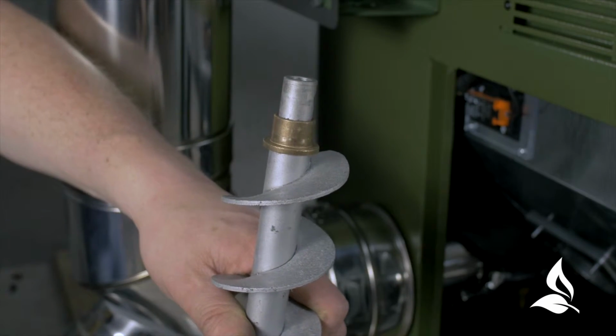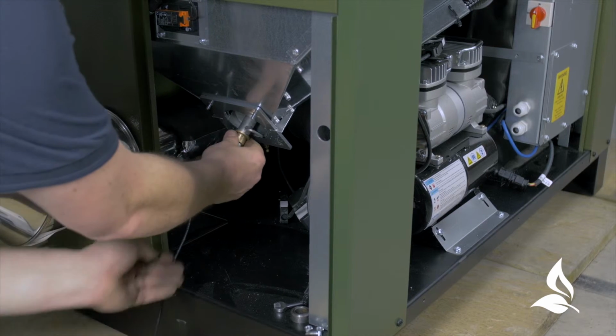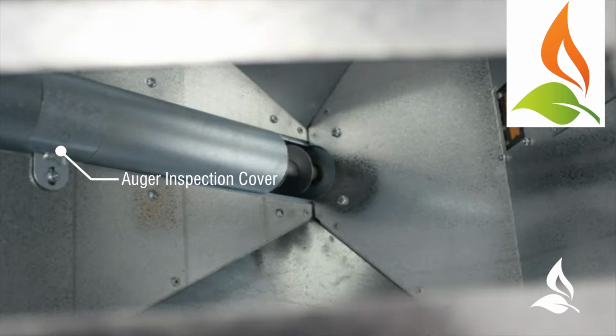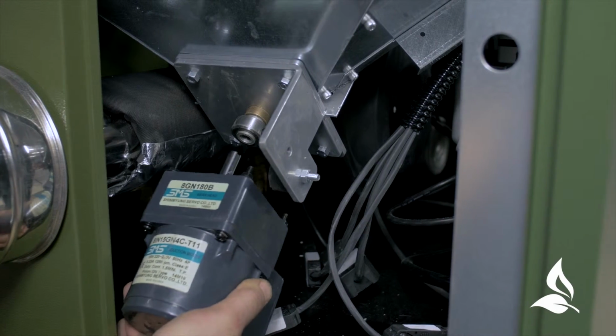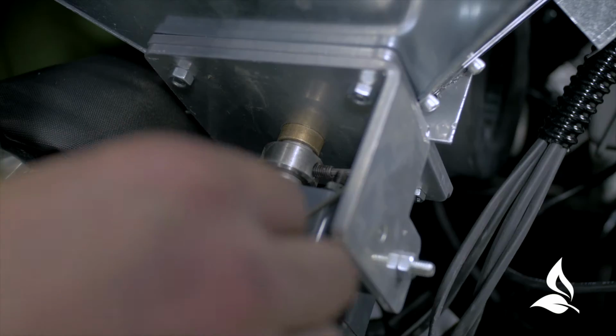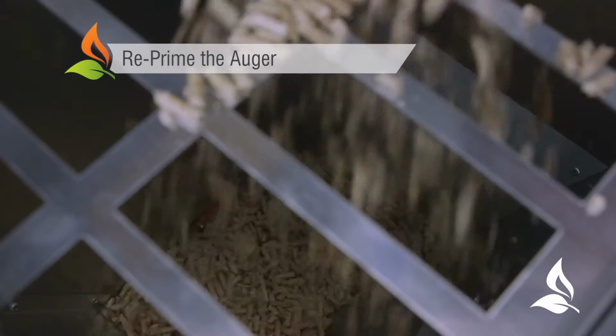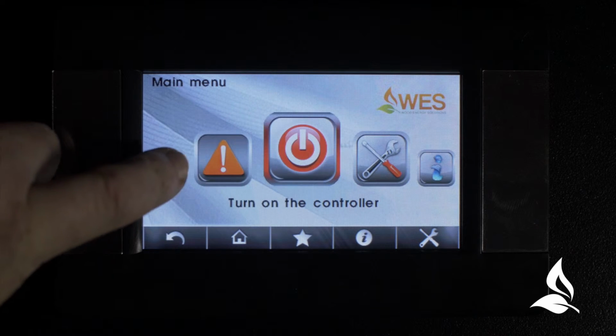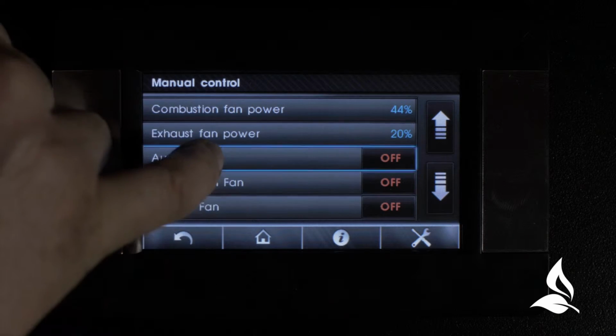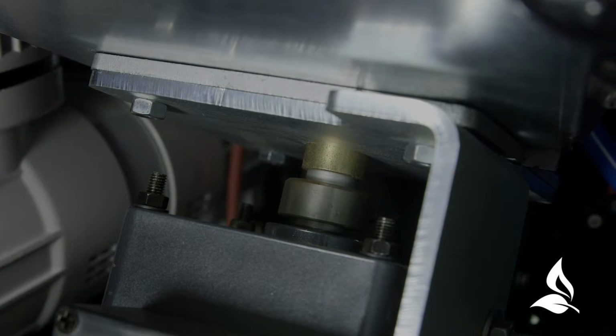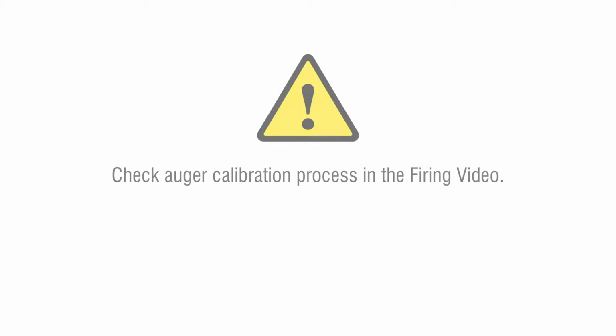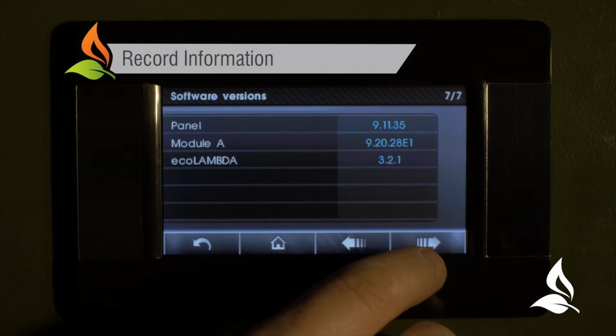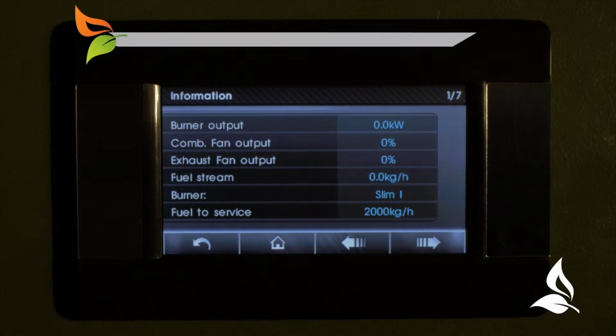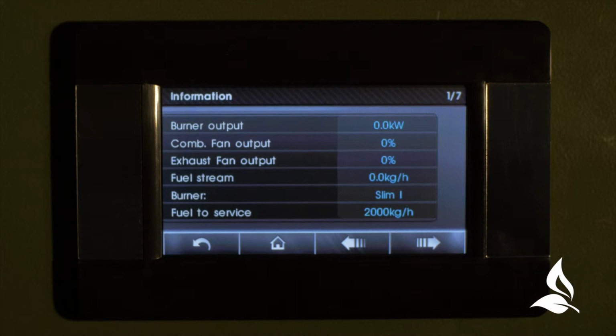Check the auger bushing. To put the auger back in, you need to remove the inspection cover off the auger housing in the hopper. Guide the auger shaft into the top bushing and fix the motor bracket back in place. Reprime the auger. Refill the hopper with fuel and reprime the auger by going into the manual control menu as shown. Check the auger calibration process in the firing video. Record the information from the counters menu and forward the details to Wood Energy Solutions.